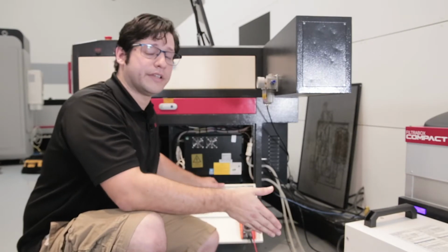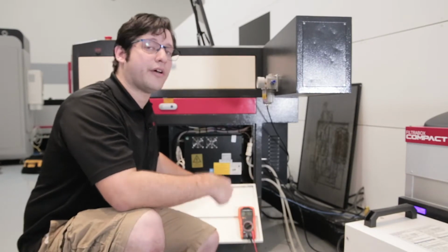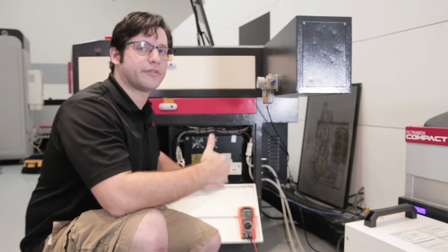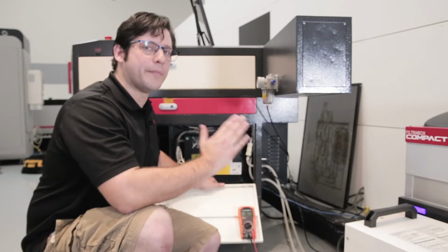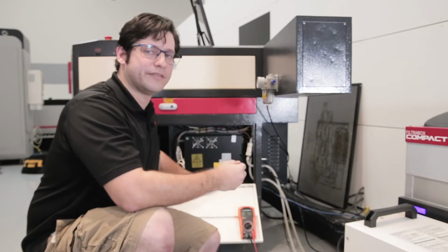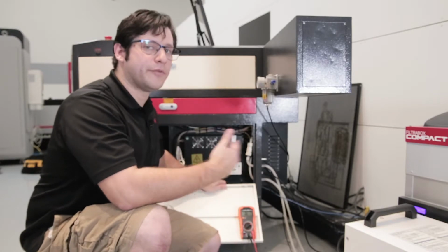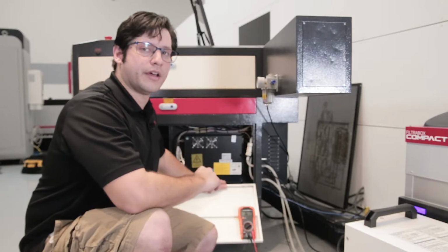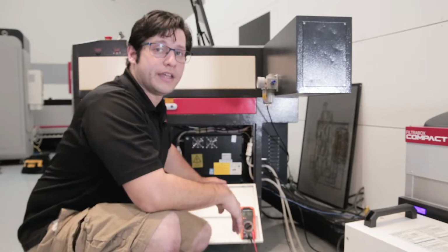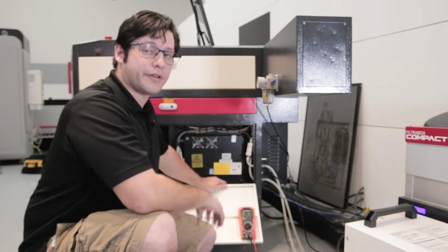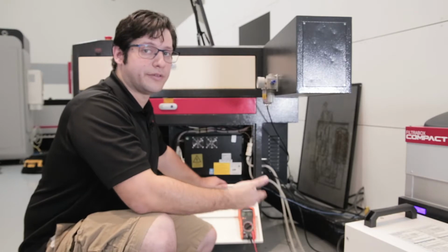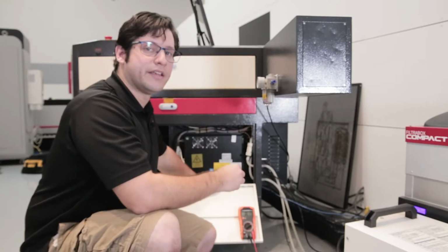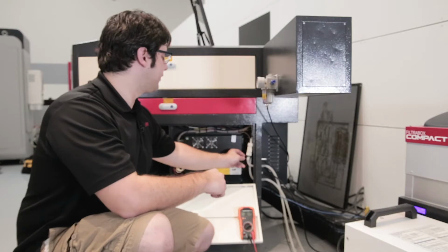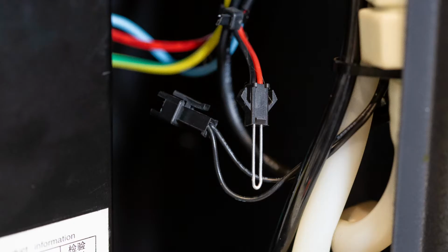So if you have continuity on your water flow sensor and you also had continuity on your door interlock, go ahead and put this back together. Go ahead and plug it back in to its connection here, and then move on to checking your chiller cable signal. If you didn't have continuity on the water flow sensor and also not on the door interlock, go ahead and place a pin inside the female plug here, just like you have on the door interlock, and then also continue to move on to your chiller signal.